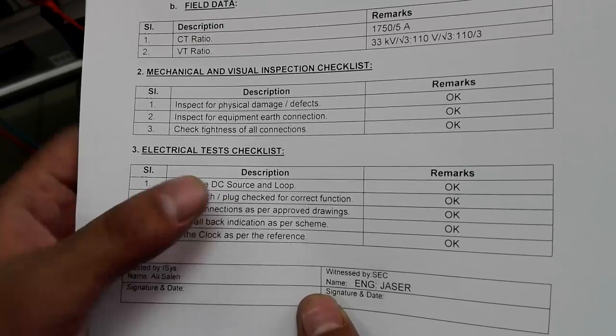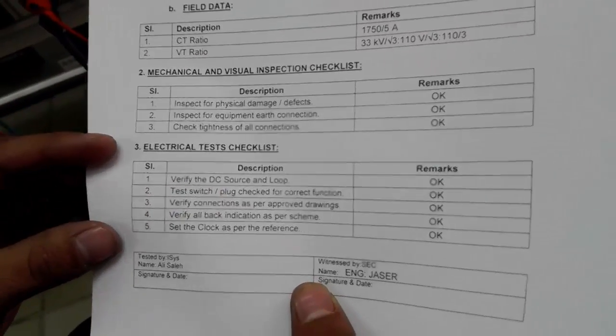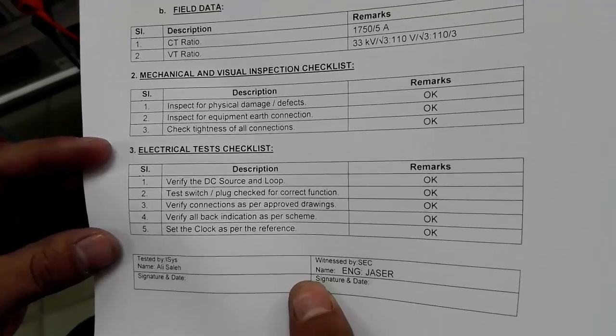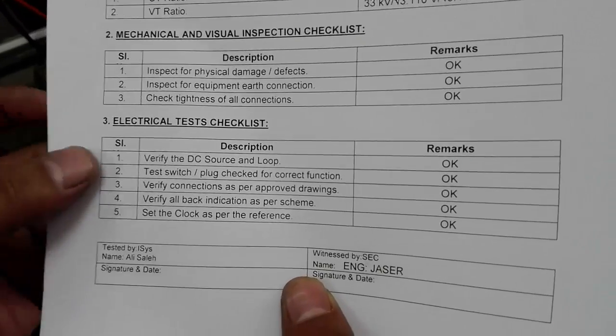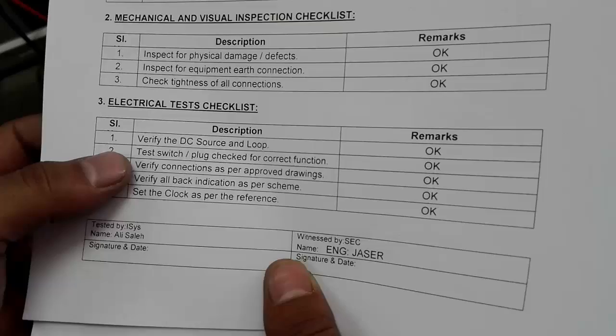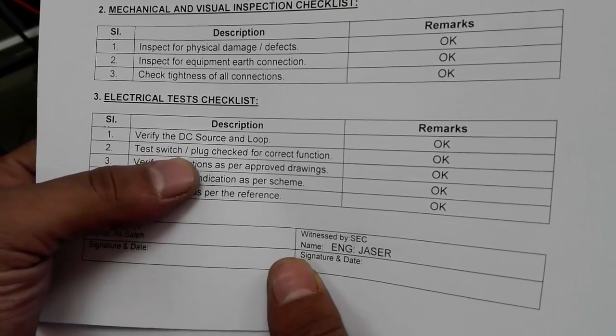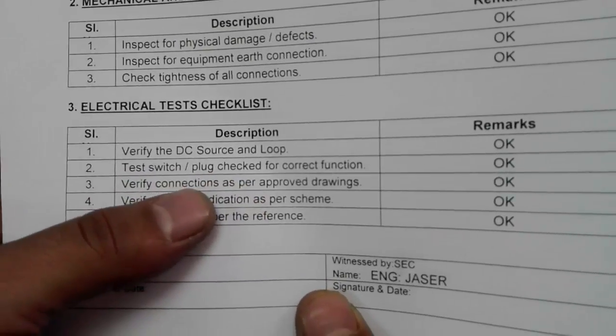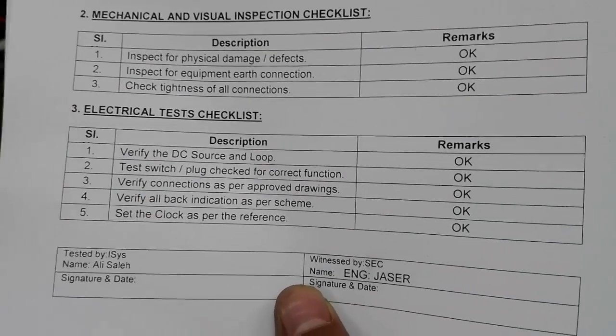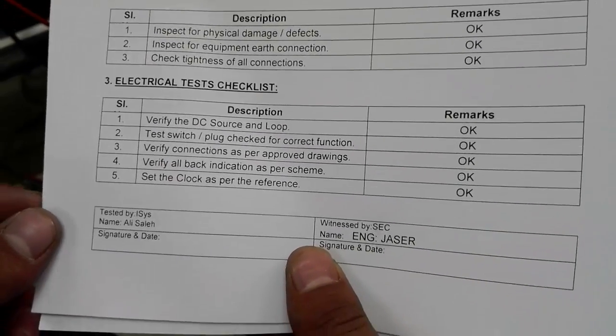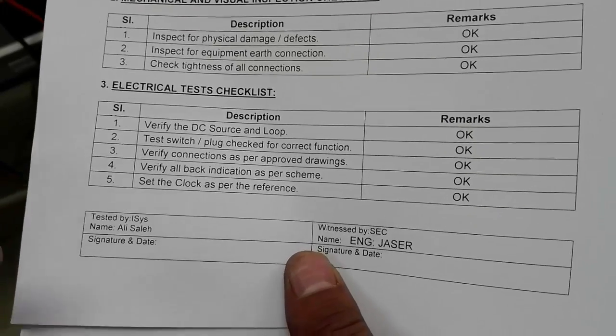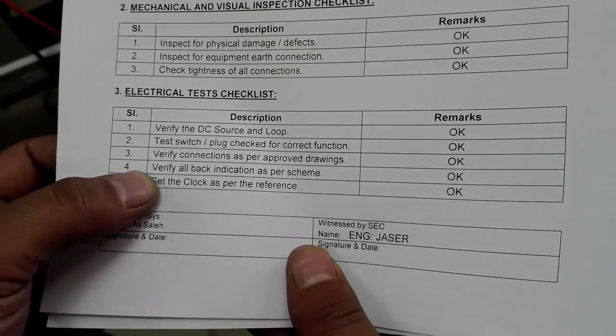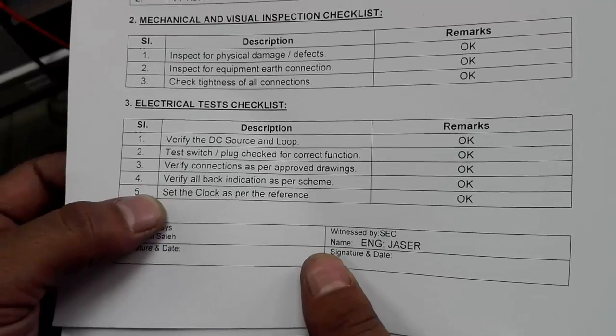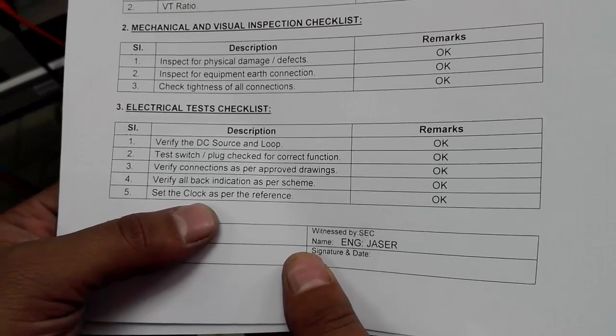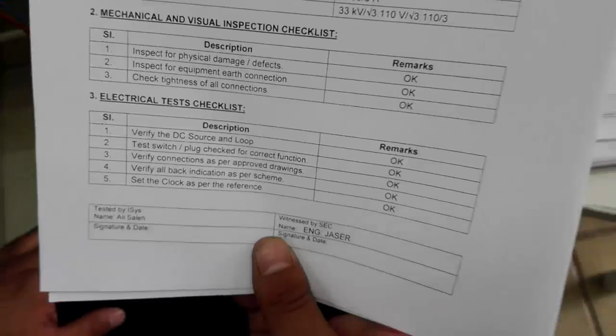Verify the DC source and loop. All this we have to do before applying volts. So verify the DC source and loop, test switch plug checked for correct function, and check whether it is connected according to the drawing or not. Verify connections as per approved drawings. Same, verify all back indication as per scheme. Set the clock as per the reference. It is to be done through software.